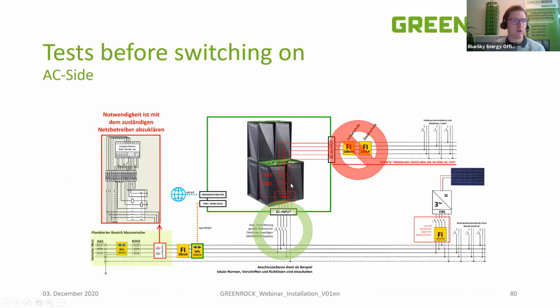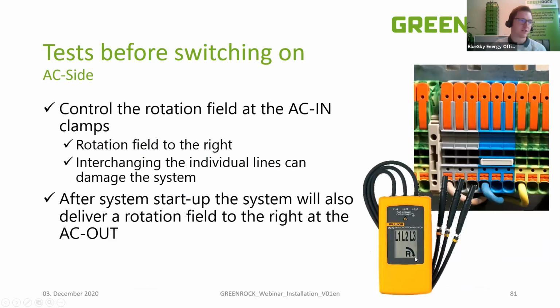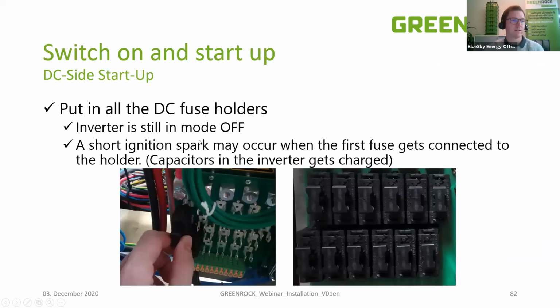Also, always check the AC in connections, that you have the correct phase rotation on the AC clamps. As soon as this is done, you can put in the fuse holders. In silver, these are the holders themselves, and in black, the fuse is placed inside. You just push it in to have it fused, and if you pull it out, it's unfused.